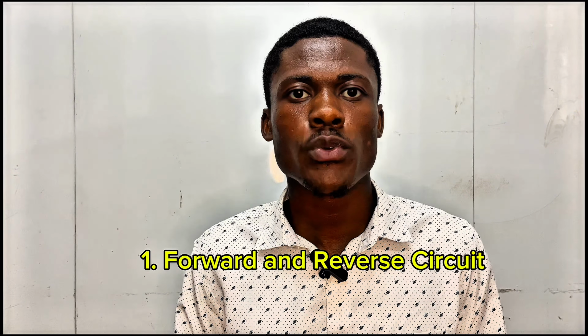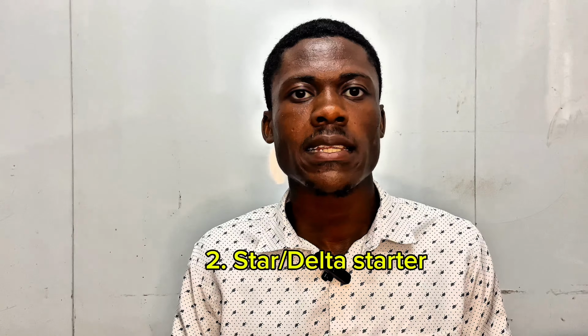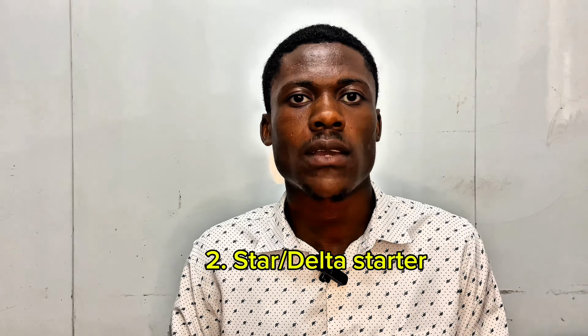We are actually going back to the studio to practically do the connection. And guys, before you go back to the studio or the workshop to practically build interlocking circuits, you have to bear in mind that we have a lot of circuits that need interlocking. I'm only going to mention three. We have the forward and the reverse system. There's interlocking between these two contactors, that is the forward contactor and the reverse contactor. That is one. We have the star delta starter. There's interlocking between the star contactor and the delta contactor. That is two. And finally, the ATS.